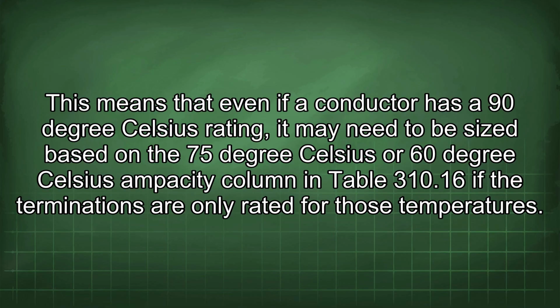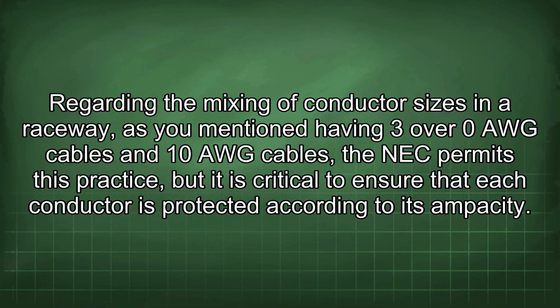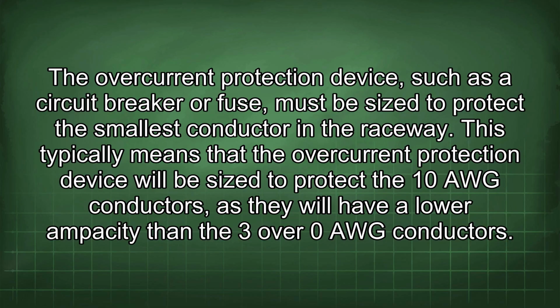Regarding the mixing of conductor sizes in a raceway, as you mentioned, having 3/0 AWG cables and 10 AWG cables, the NEC permits this practice, but it is critical to ensure that each conductor is protected according to its ampacity. The overcurrent protection device, such as a circuit breaker or fuse, must be sized to protect the smallest conductor in the raceway. This typically means that the overcurrent protection device will be sized to protect the 10 AWG conductors, as they will have a lower ampacity than the 3/0 AWG conductors.